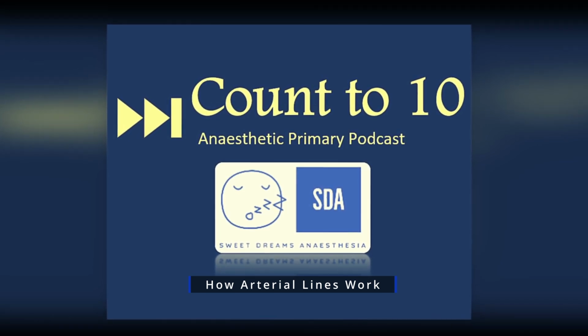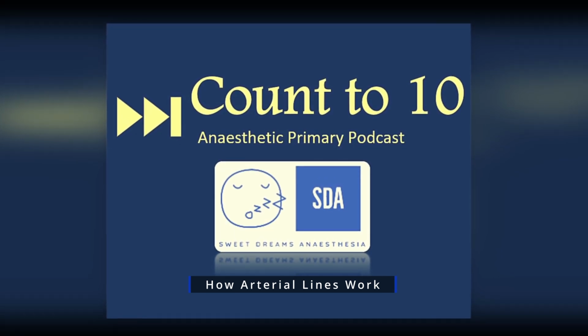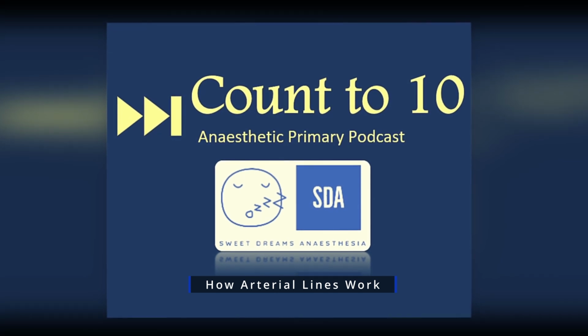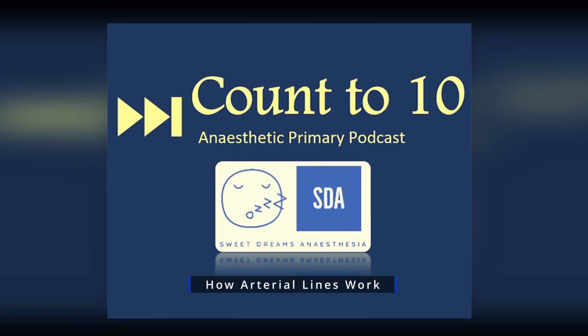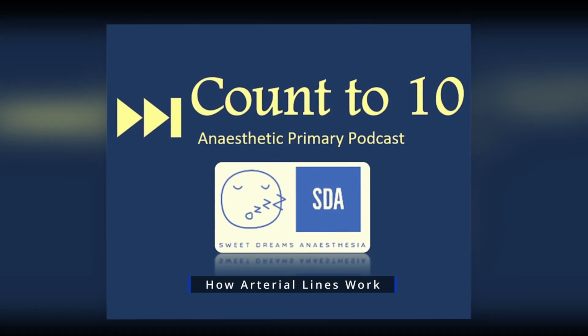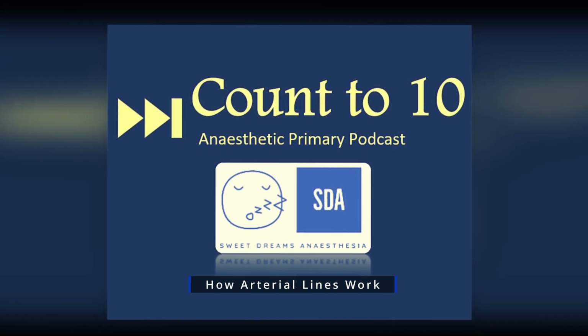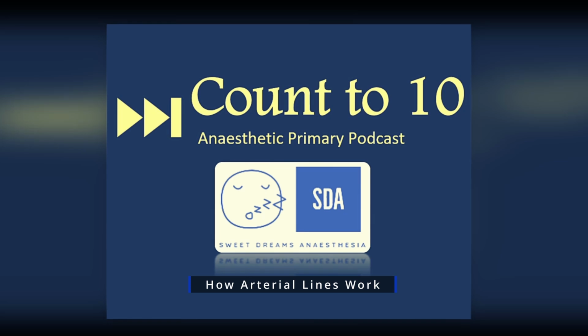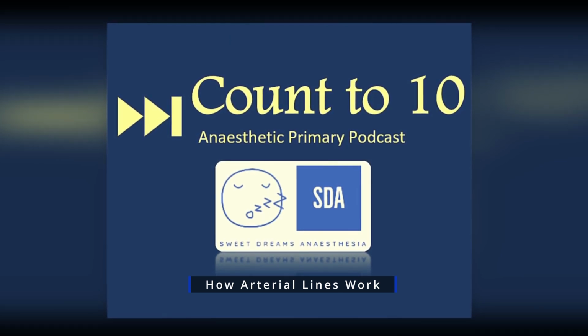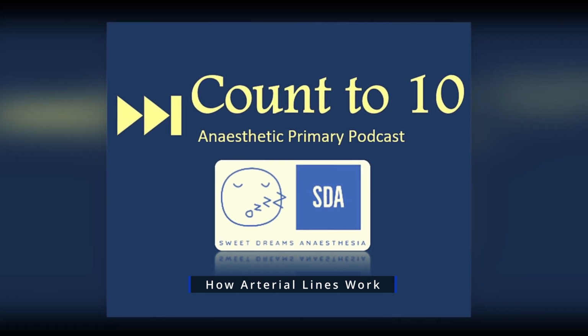line works. To me, the most important thing to understand with an arterial line is that it is taking energy in the form of pressure, being from the blood, and converting it to electrical energy, and that electrical energy is going through an analysis which is then giving us an output. Therefore, the components we have to get us to that point include a sensor, being the transducer, an integrator, being the module where the analysis is occurring, and then the output, which we see as both a number and a waveform on our screen. So how do we get to this end result?